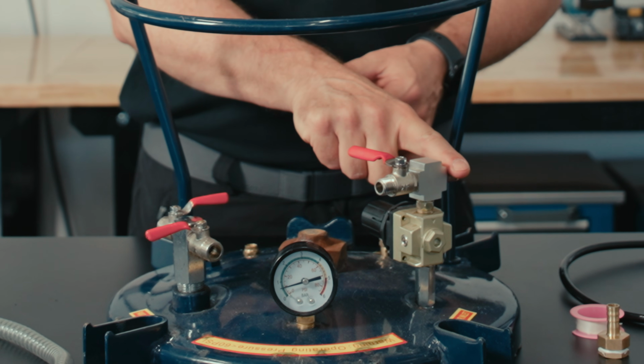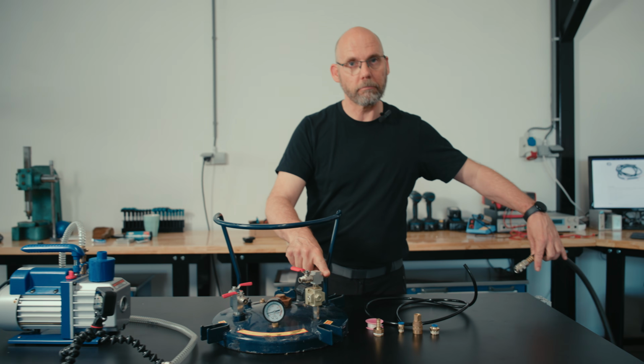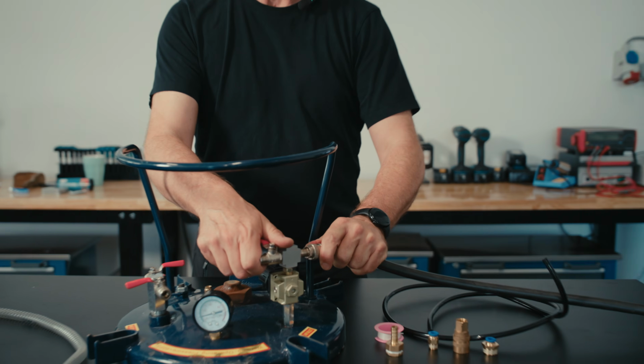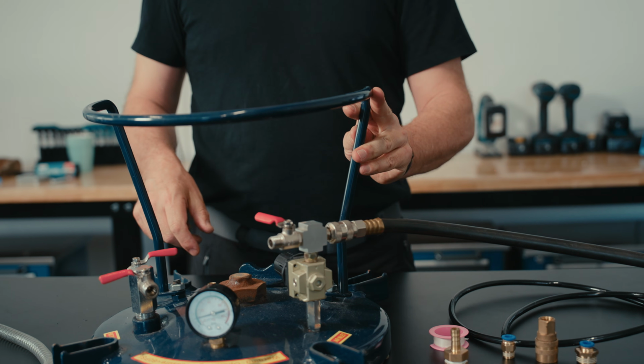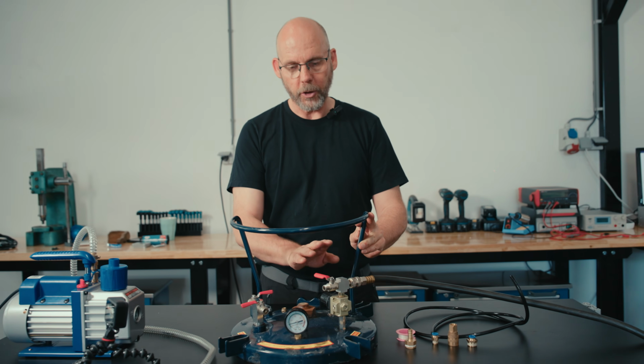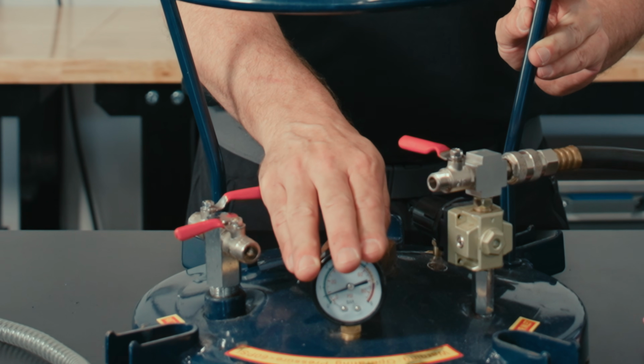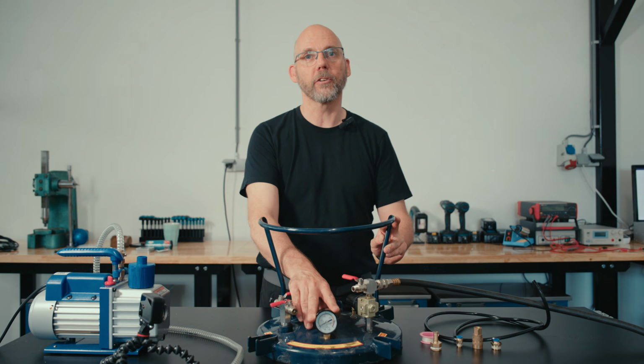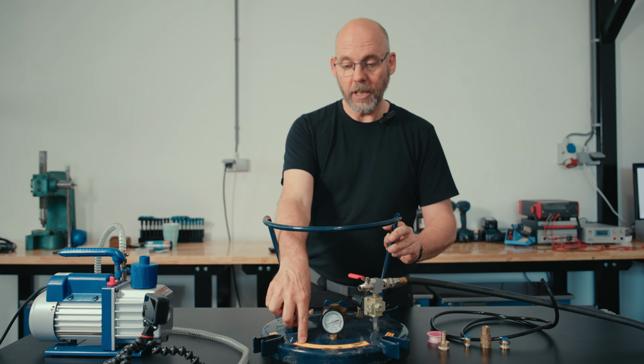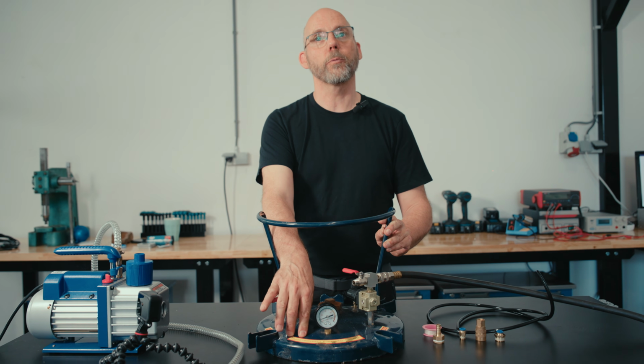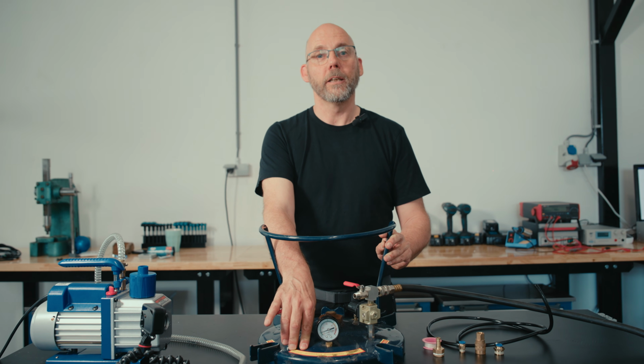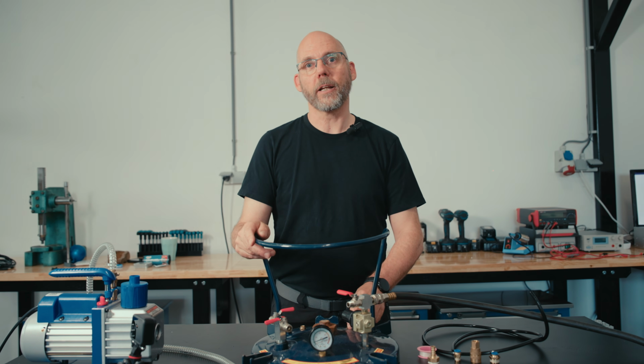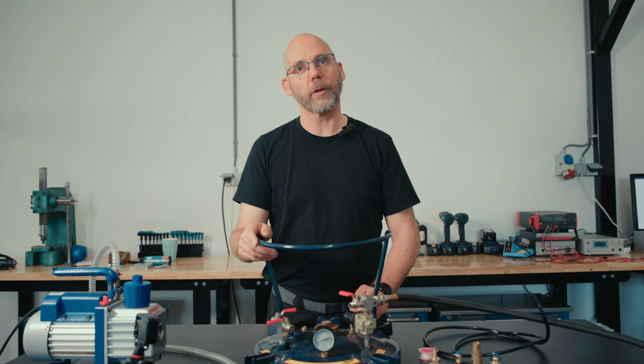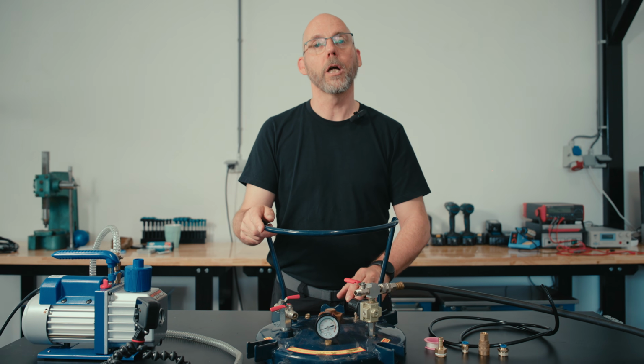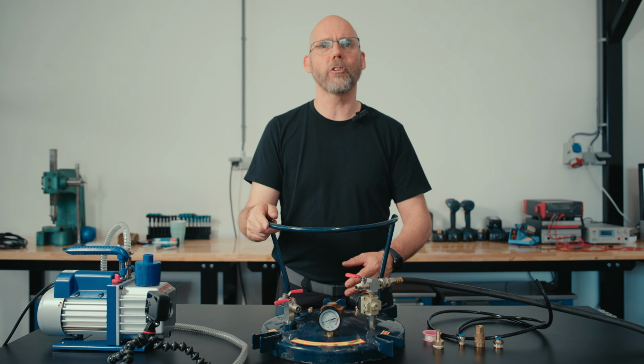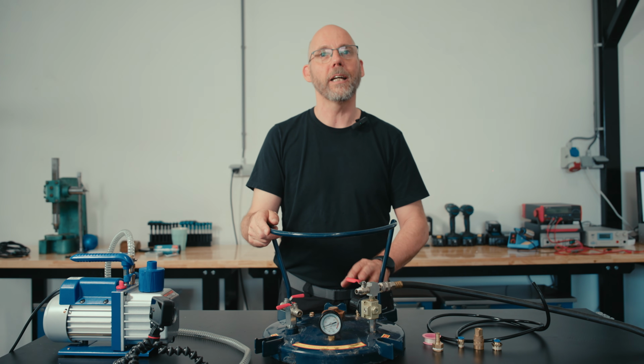On this connection right here, we'll be connecting the compressor with a simple air line, as normal. We can adjust the pressure, see it on the gauge, and not go beyond the rated pressure. In this case, stay below 60 psi, which is what the pressure pot is rated for. There's also a safety valve right here to make sure it's secure. We'll be testing it in a minute, but don't modify that. Don't paint over it, don't put a piece of tape on it, don't remove it, keep it there. It's important.